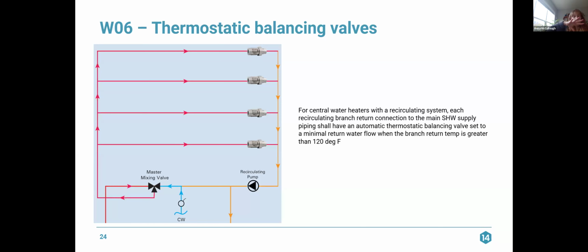We know that our condensing water heaters and heat pump water heaters operate at a higher efficiency when return water temperatures are lower. So we're going to reduce the demand there and return less hot water into the return piping. And here's an example of, these are the little thermostatic balancing valves, reducing the flow into the return water because the water's too hot.